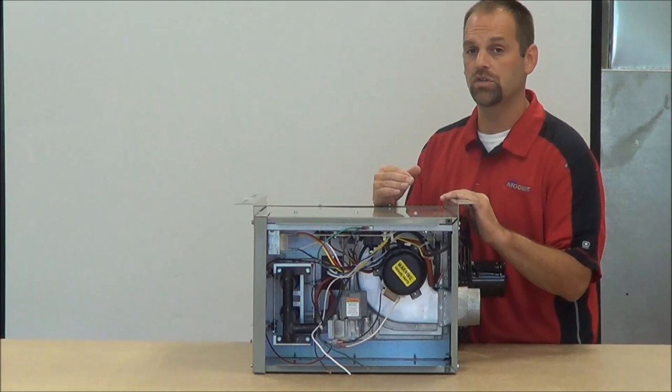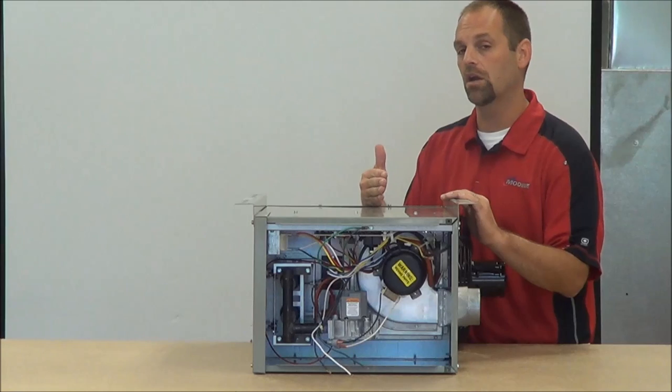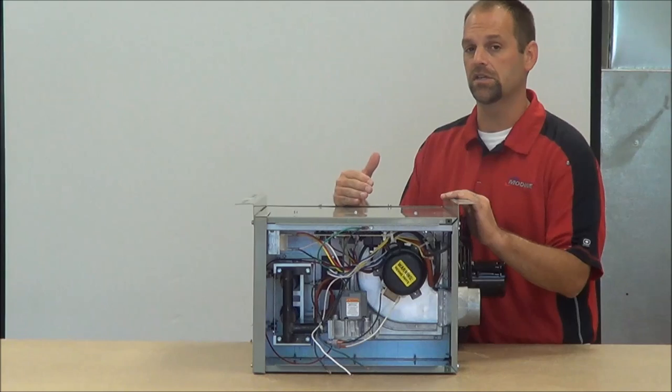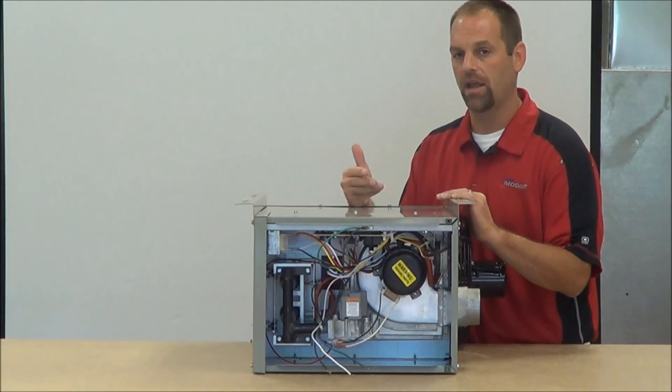That's one of the most common issues we see when a unit will start off, run for a few seconds and drop off. A very simple test, a very simple fix, is to flip the wires and let it run.